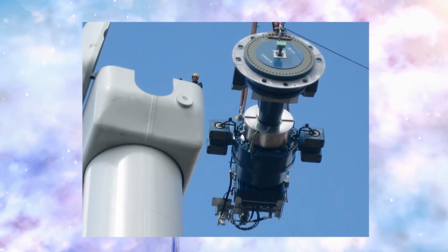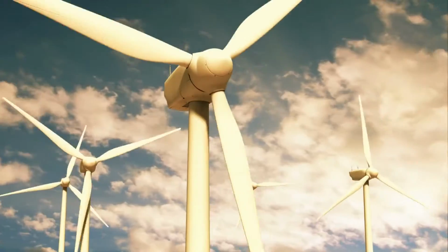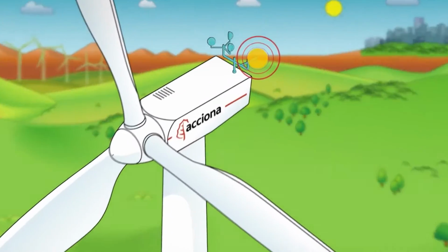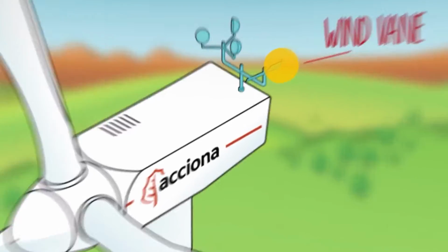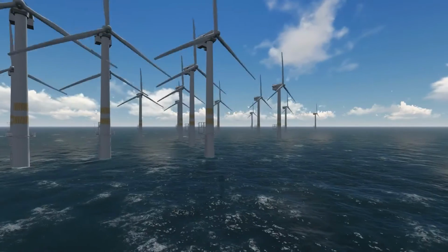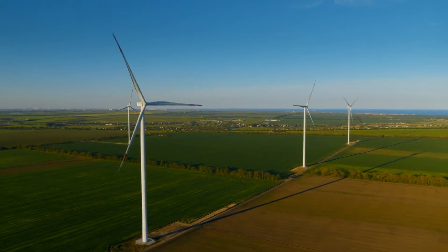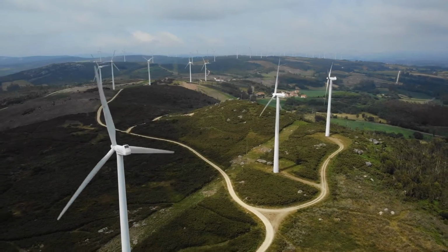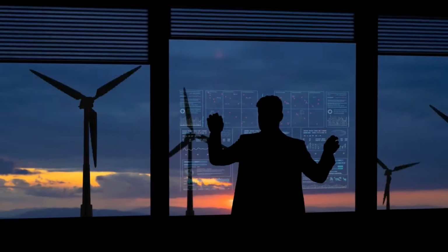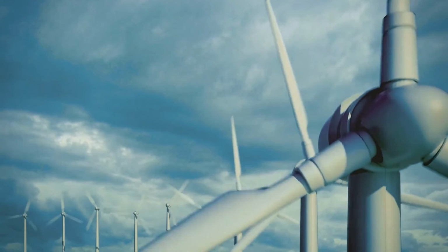The nacelle, also known as the head, has a wind vane, an anemometer, and a controller that measures the wind speed and direction. When the wind direction changes, a motor spins the nacelle to ensure the blades face the wind. In high winds, a brake on the turbine slows the speed of the shaft. In extreme situations, the brake protects the turbines from harm. Horizontal axis turbines have 3-blade airplane propellers. The largest is approximately a 20-story structure with 100-foot-long blades. The more electricity produced, the taller the turbine. The horizontal form is nearly universally utilized in turbines.